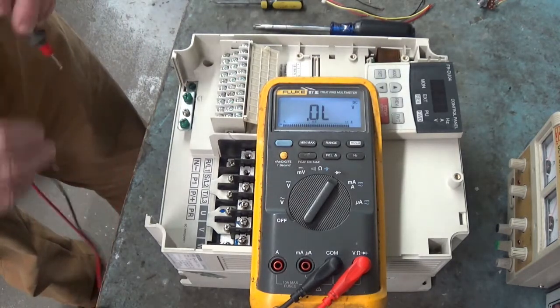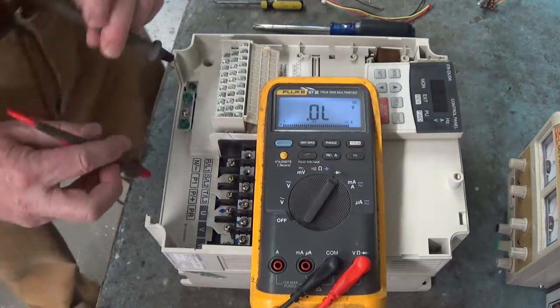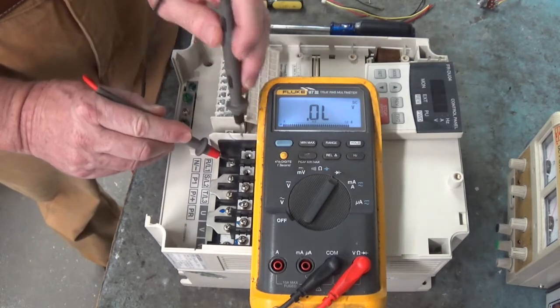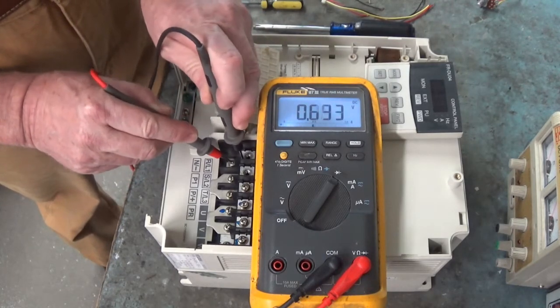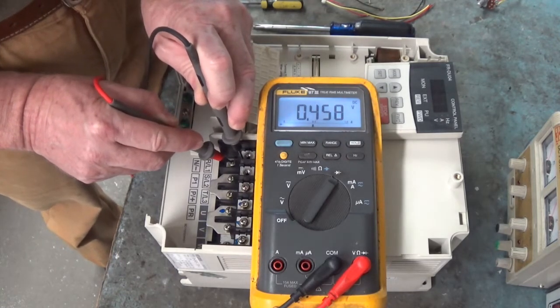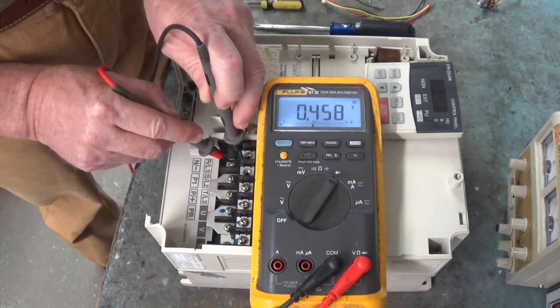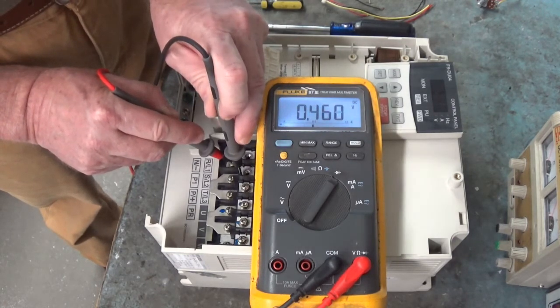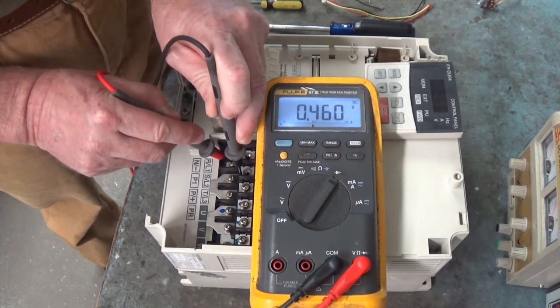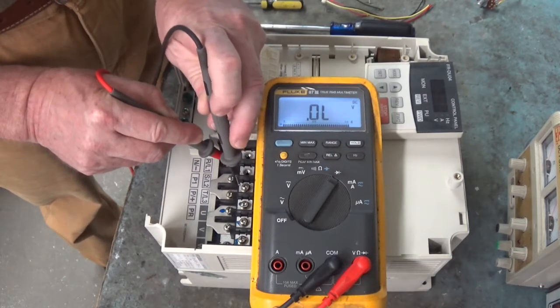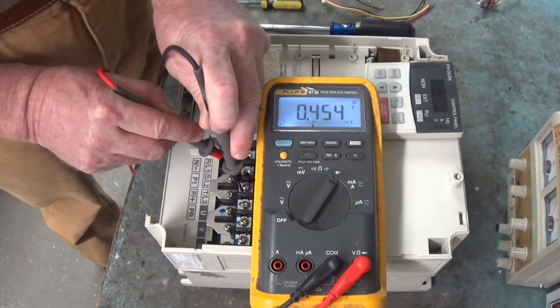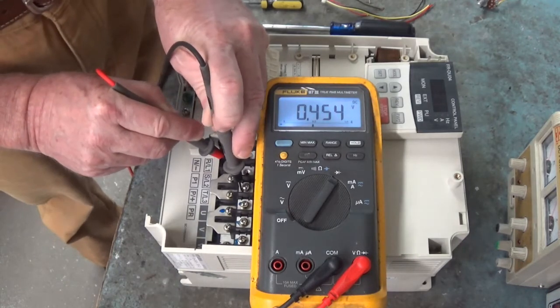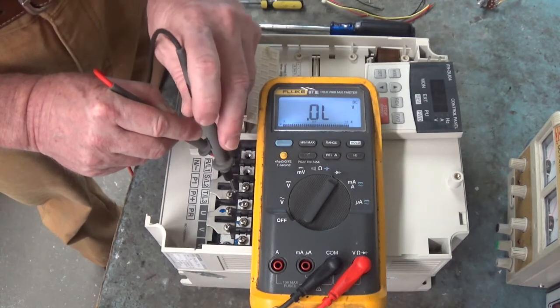So let's take our red lead and put it on N slash minus. We'll take our black lead and put it on R slash L1. We'll go 0.459. That's a good diode drop right there. Let's take our black lead and move over to S slash L2. There again, 0.460. That's good. Move our black lead to T slash L3. 0.454. That's a good diode drop. It's not shorted. Your line voltage coming in is not shorted.